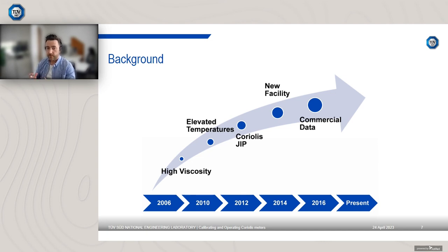However, we started to get asked about other effects on Coriolis meters. Now, Coriolis meters are fantastic devices, mass measurement devices. They also offer volumetric measurement because they also directly measure density. So they give you mass flow, volume flow, and density. And there was always the understanding that Coriolis meters weren't overly affected by process conditions. That's certainly true with respect to installation, upstream and downstream straight pipe requirements. But there does appear to be an effect of viscosity, pressure and temperature.